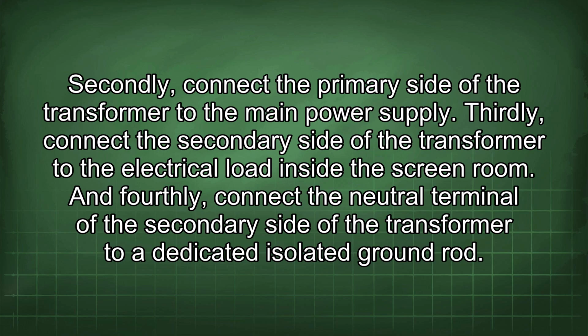Secondly, connect the primary side of the transformer to the main power supply. Thirdly, connect the secondary side of the transformer to the electrical load inside the screen room. And fourthly, connect the neutral terminal of the secondary side of the transformer to a dedicated isolated ground rod.